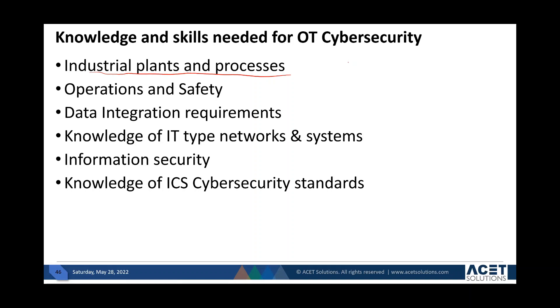A client may have 100 PLCs and want to know which are most critical. One PLC might control a water treatment facility while another controls water distribution — with five treatment plants and ten distribution points, which is more critical? Unless you understand the processes, you can't judge that. You also need to learn about operations and safety constraints, because in a plant environment safety is paramount. Any safety incident affecting people or equipment is not tolerated. You must also understand data integration requirements: how do control systems integrate with IT and business systems, and what types of data and communication are required?